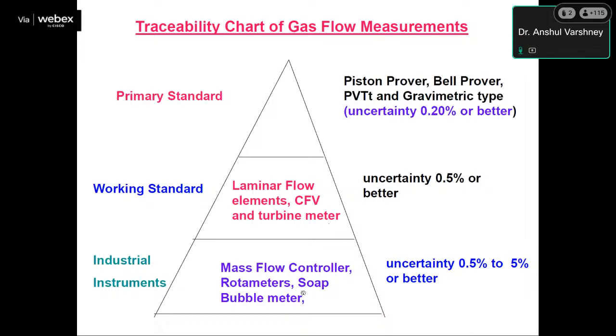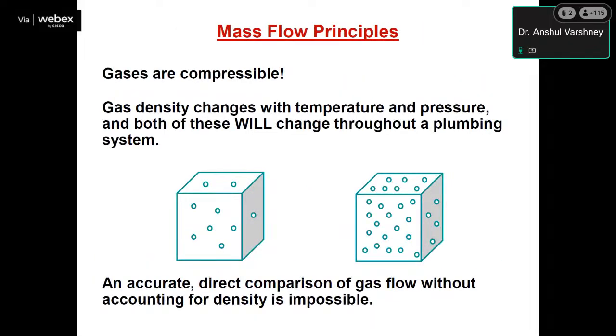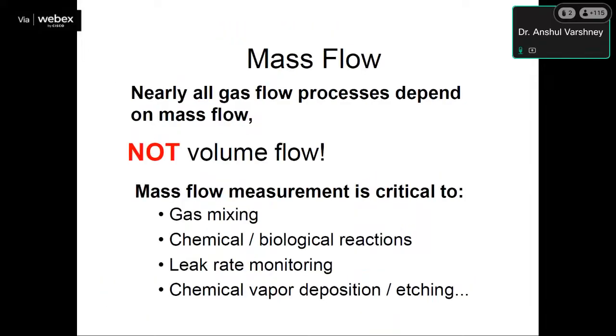Uncertainty is 0.5% or better. And as industrial instruments, the mass flow controllers, rotameters, and similar meters have uncertainty between 0.5% and 5%. Gases are compressible, as we all know. Gas density changes with temperature and pressure, and both of these will change throughout a plumbing system. An accurate direct comparison of gas flow without accounting for density is impossible.